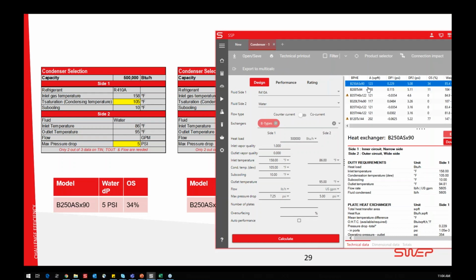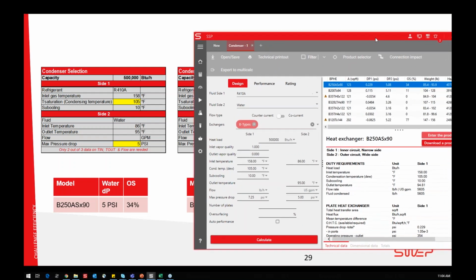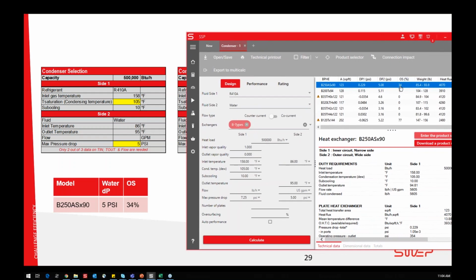B250AS, so an asymmetric heat exchanger. It makes sense. It's a condenser, with refrigerant and water, with 90 plates. Yep. What I want to point out this time is the oversurfacing. This heat exchanger, SWEP SSP says it's oversurfaced. There is more surface than needed to meet the thermal conditions, but SSP added plates to be able to reach the 5 psi limit here.